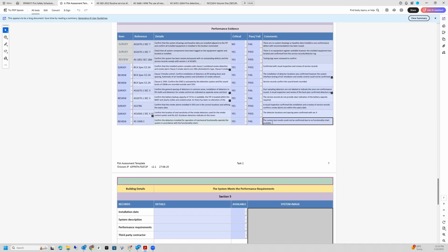Look, it would take me a long time to go through 1668 and 1670 and the building code, all three of those documents, to actually determine how this system is supposed to function based on what the performance requirement is. And somebody should have done that and already provided me under the design the functionality chart. If that's not available, guys, then really you can't pass it. You may be able to test it.